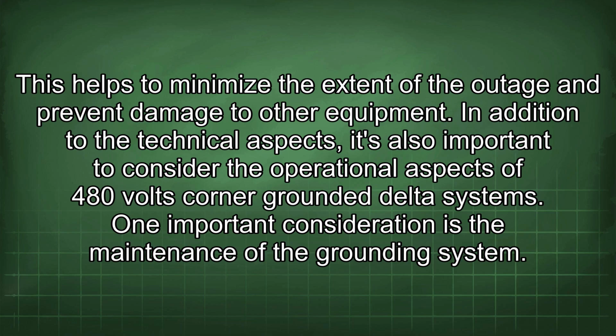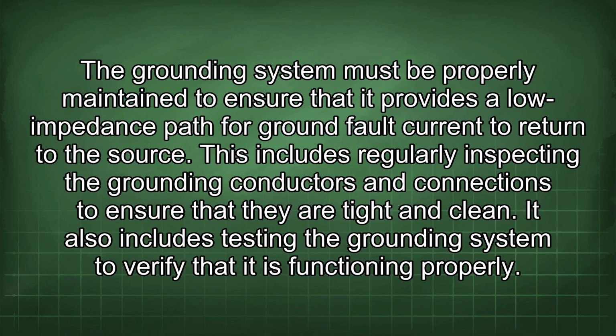In addition to the technical aspects, it's also important to consider the operational aspects of 480 volts corner-grounded delta systems. One important consideration is the maintenance of the grounding system. The grounding system must be properly maintained to ensure that it provides a low impedance path for ground fault current to return to the source. This includes regularly inspecting the grounding conductors and connections to ensure that they are tight and clean. It also includes testing the grounding system to verify that it is functioning properly.